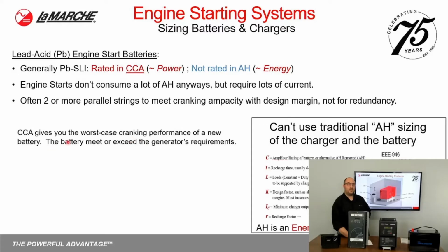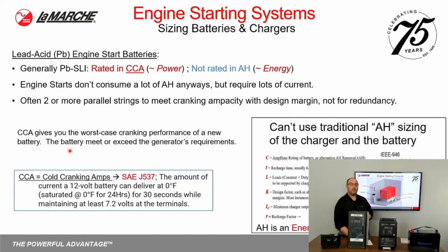So cold cranking is a really nice system because it gives you the worst case cranking performance of a new battery. The battery that you choose and select for the system must meet or exceed the generator's requirements. You really can't have too large of a cold cranking amp rating on an engine start application. So let's look at that.